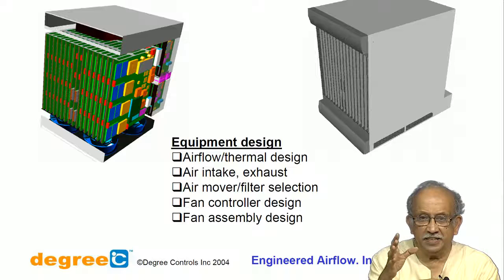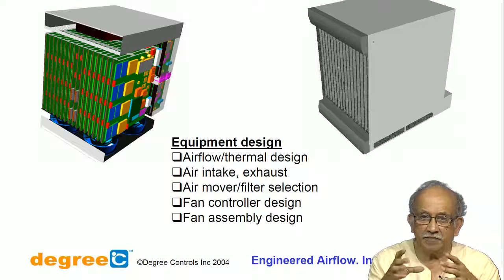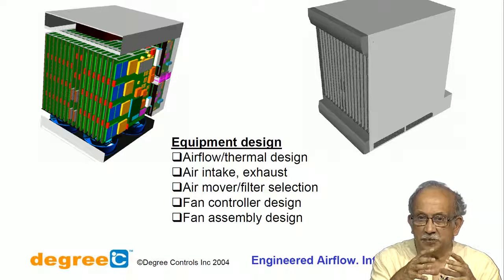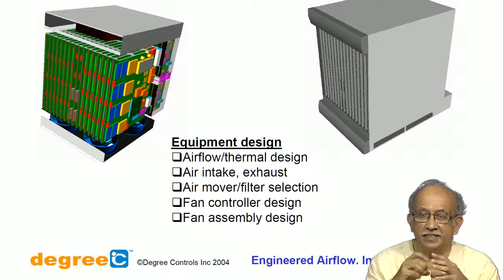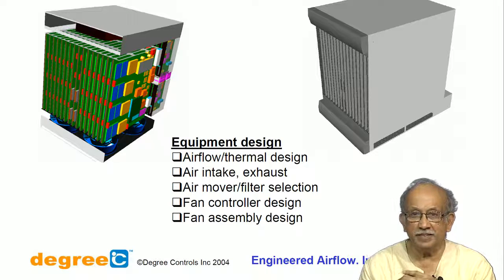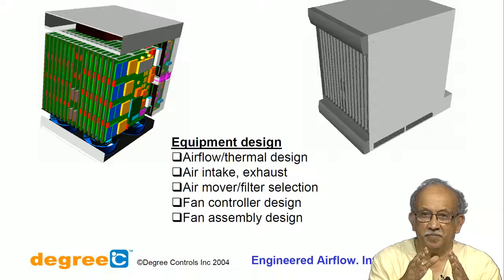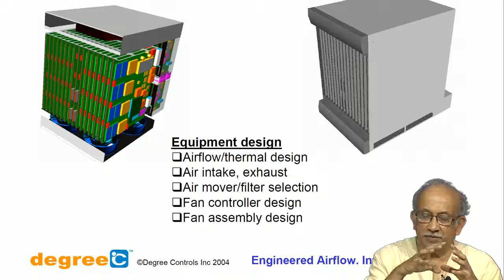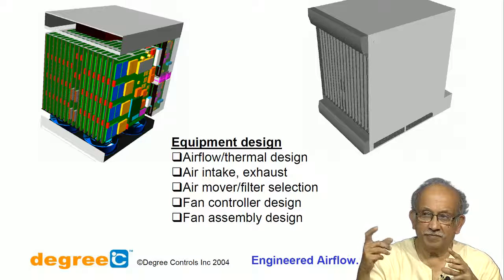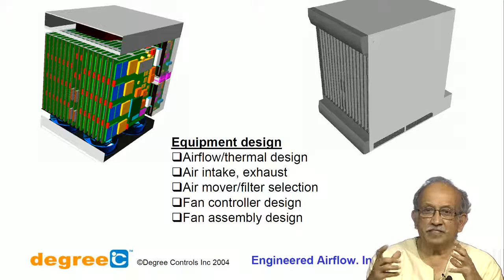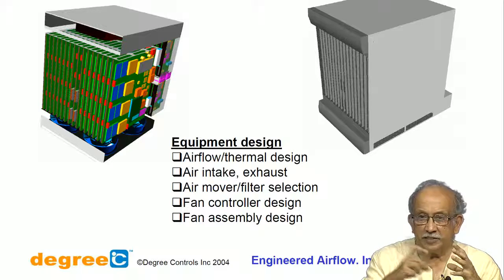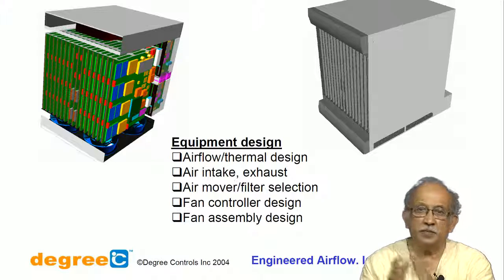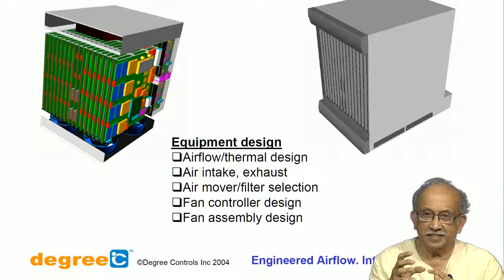An alternative is a bellows-like filter made of loosely spaced mesh material coated with a viscous, oil-like liquid. These corrugated mesh filters are sprayed evenly with a slightly viscous oil, allowed to rest, and when placed back in the equipment the incoming air causes dust to get trapped in the coating. The pressure drop is low, and this type of filter can be recoated and reused.